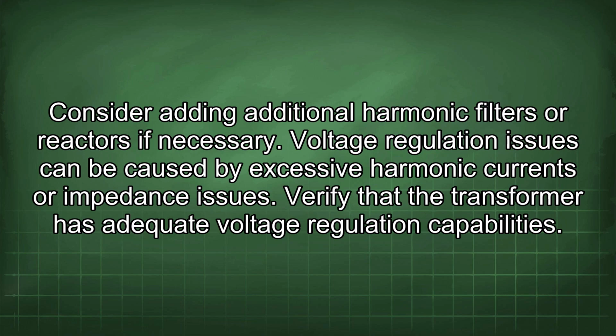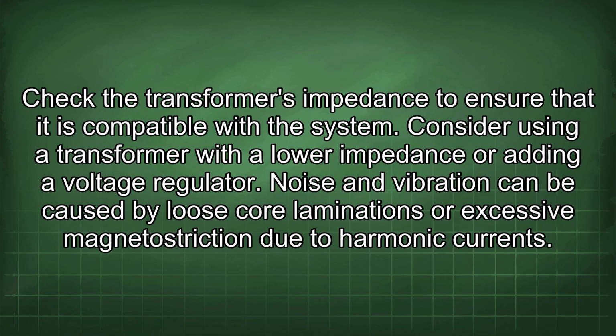Voltage regulation issues can be caused by excessive harmonic currents or impedance issues. Verify that the transformer has adequate voltage regulation capabilities. Check the transformer's impedance to ensure that it is compatible with the system. Consider using a transformer with a lower impedance or adding a voltage regulator.